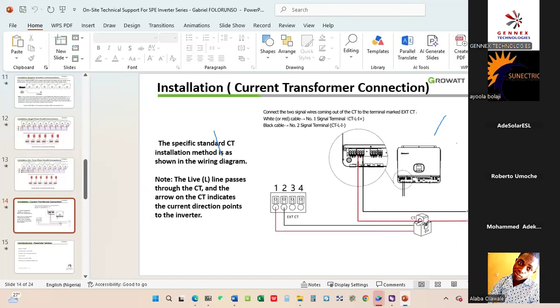The good news is there is no rule here, because for the transformer you only have start and end, so you can put any color there and it will still work. But you only pay attention to the arrow inscribed on the CT, and that arrow should face the word inverter. Also, you should clamp only the live wire.